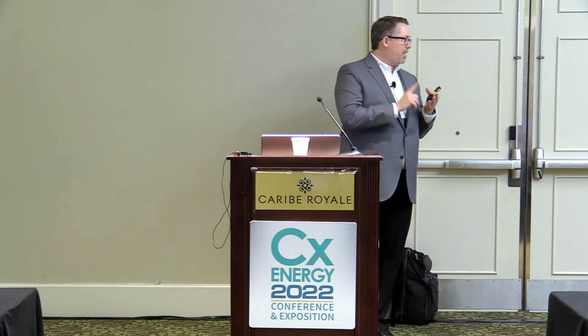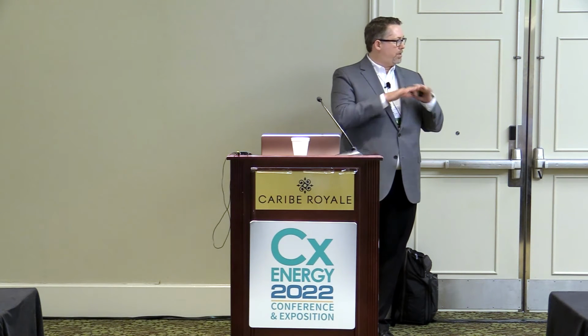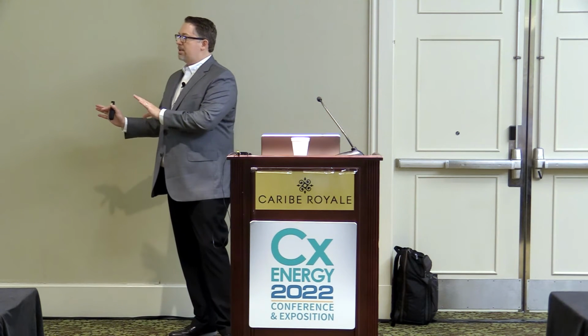more challenging. And I wrote here that balancing is potentially the most challenging portion of the hot water delivery system. When you have a properly balanced system, you're able to get and maintain hot water temperatures throughout. So if you're getting the right water temperature quickly in certain parts of your building, but long wait times in other portions of your building, that is most likely a key indicator that your system is not balanced properly.